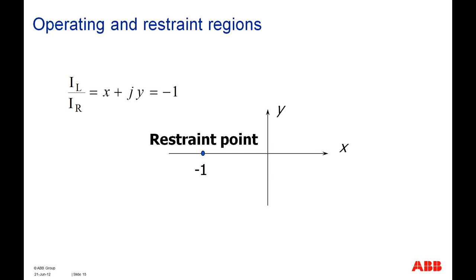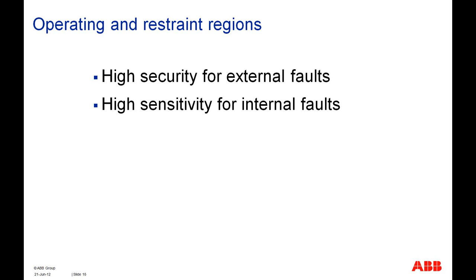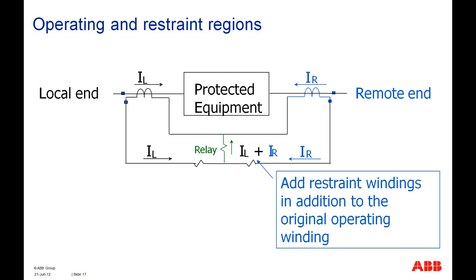And that would be in the operating and restraining region, IL over IR, so that would be -1, and that would be in the restraining point. So in this case, we will have very high security for external faults, and at the same time, very high sensitivity for internal faults. But because we do not have the ideal situation, there can be some errors, and we will talk about these CTs in detail.